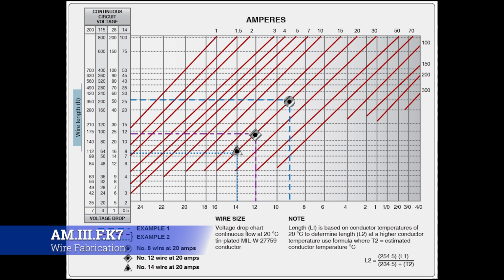So factors for selection: one, the conductor length; two, the current it's going to carry; three, the permissible voltage drop per engineering; four, the intermittent or continuous current; and five, the conductor temperature. What temperature do you think this conductor is going to be exposed to based on the operating area and location on the aircraft, and the installation type? Is it in a conduit? Is it in a bundle? Is it a single conductor in free air, meaning does the wire just hang somewhere? Is it in a wire bundle? Is it inside a conduit?